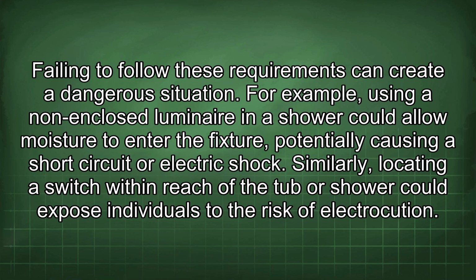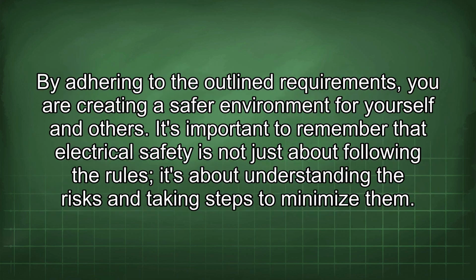Failing to follow these requirements can create a dangerous situation. For example, using a non-enclosed luminaire in a shower could allow moisture to enter the fixture, potentially causing a short circuit or electric shock. Similarly, locating a switch within reach of the tub or shower could expose individuals to the risk of electrocution. By adhering to the outlined requirements, you are creating a safer environment for yourself and others. It's important to remember that electrical safety is not just about following the rules, it's about understanding the risks and taking steps to minimize them.